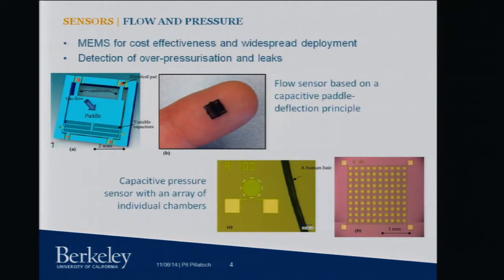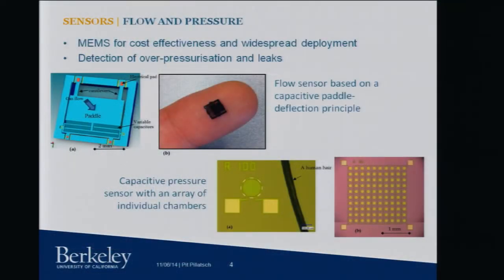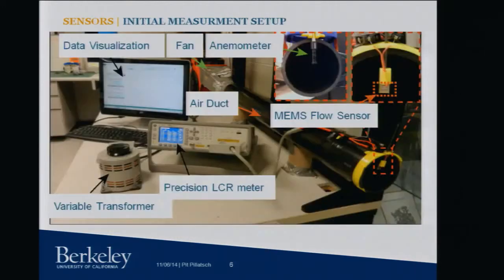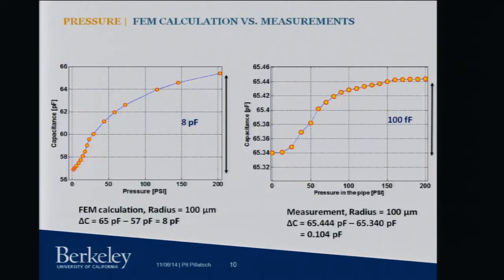So these pressure sensors, they essentially have like 100 small little capsules that all have a vacuum inside. And these capsules need to be sealed very well. And it just seems that these seals are leaking. And so currently, we're working on adjusting the process in the clean room to make sure that these seals are tight. And we are almost there to run a new batch of experiments to make sure that we get the results that the simulation actually predicted.